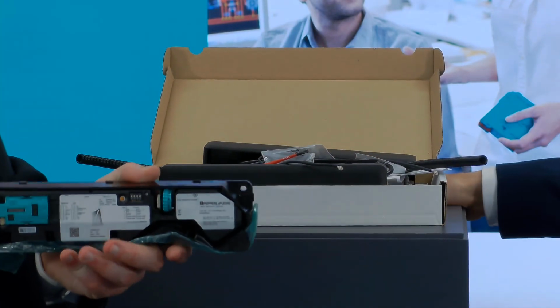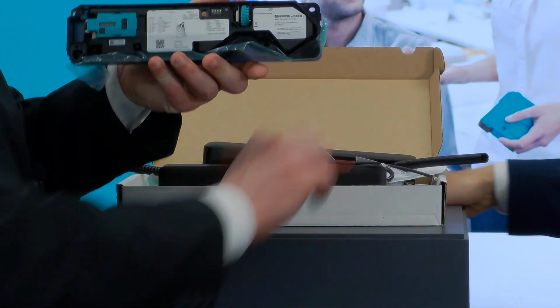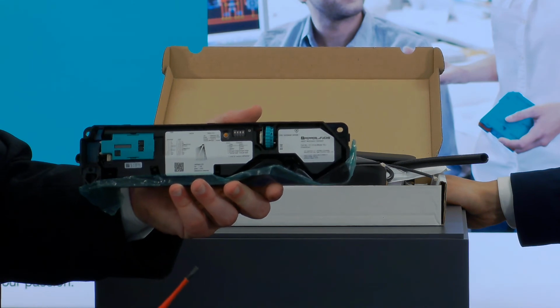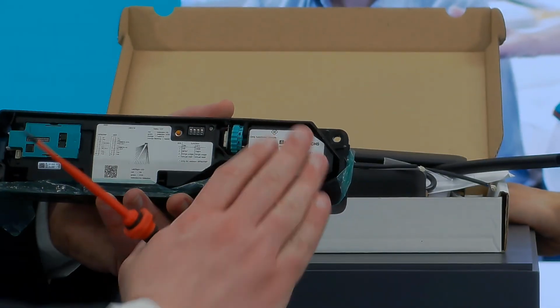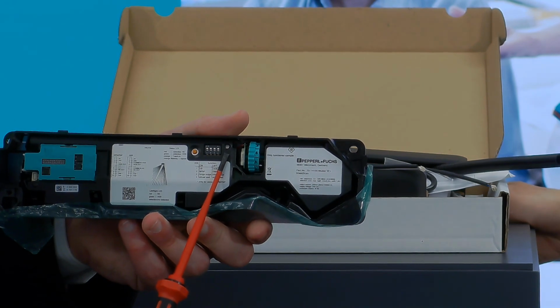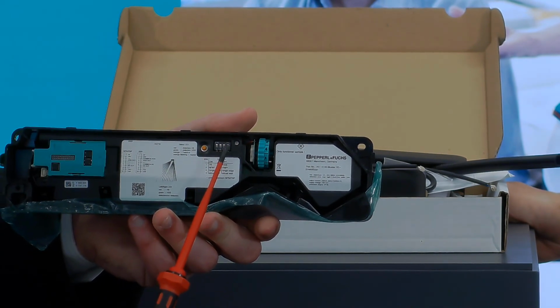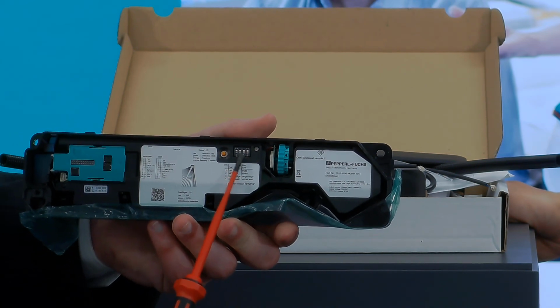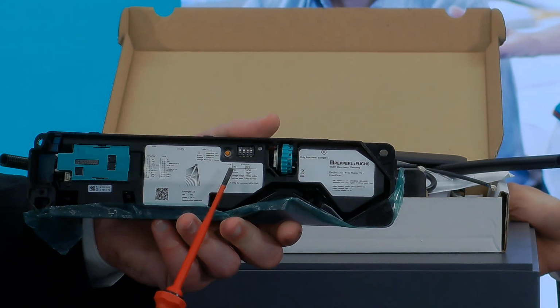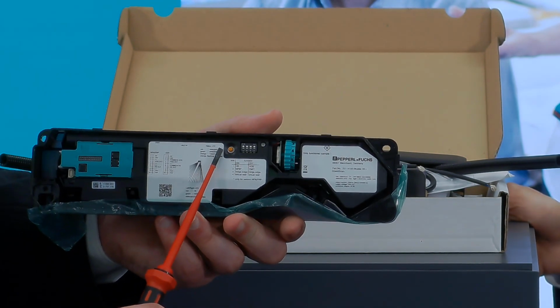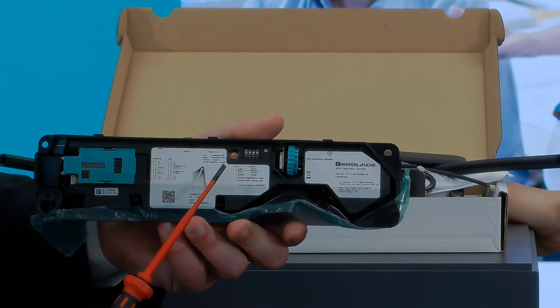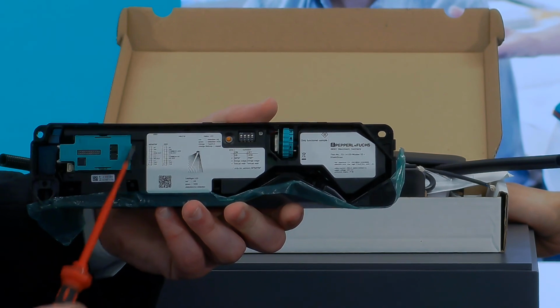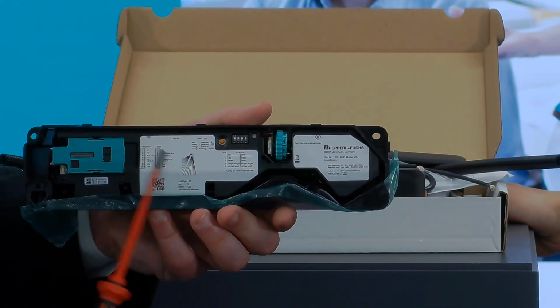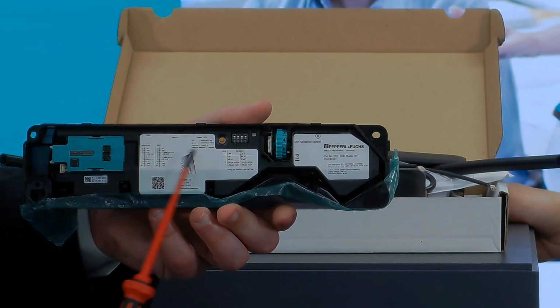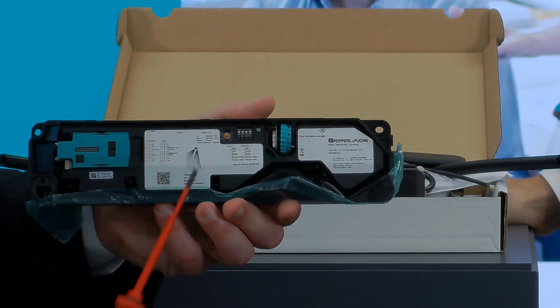Inside the sensor we find the setting controls, the control parts for doing the settings. Here is the setting dial to adjust the inclination angle of the sensor according to the height of the door. This is the small multicolor LED showing the status, and here we see the dip switches to choose the several operating modes according to the application. On this side is the teach-in button to start the commissioning procedure. Between these two parts is a quick installation guide to help the mounting personnel get a quick start setting up the sensor.